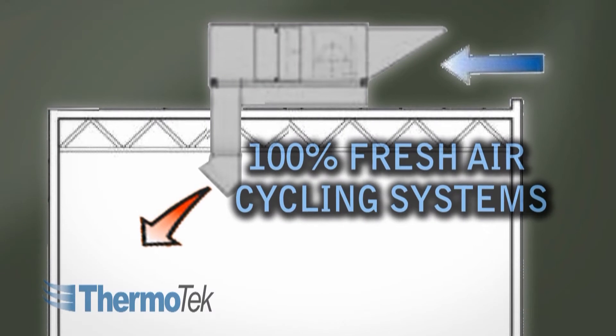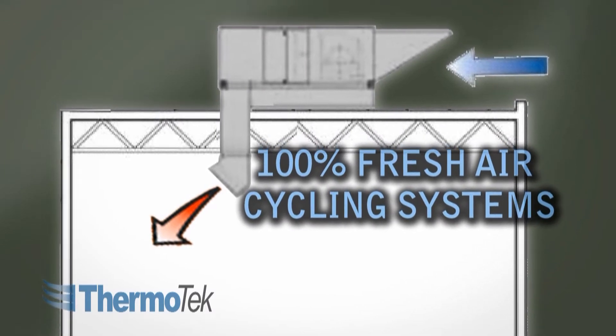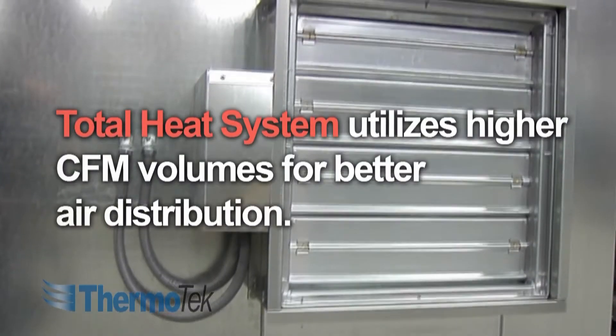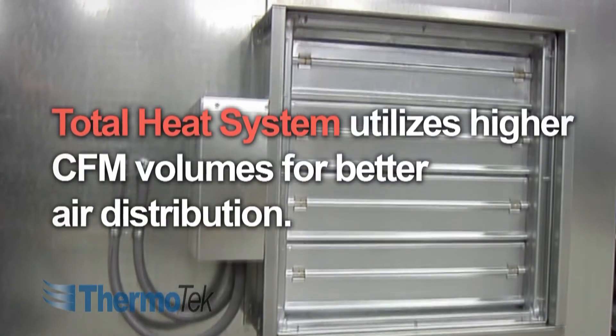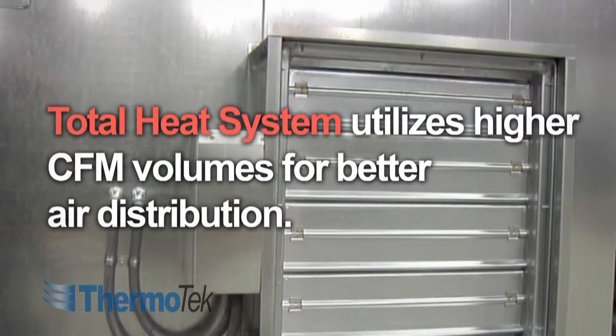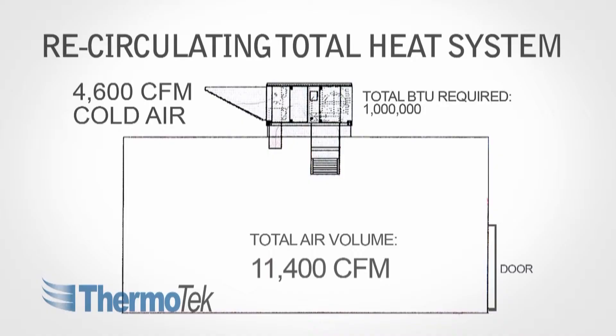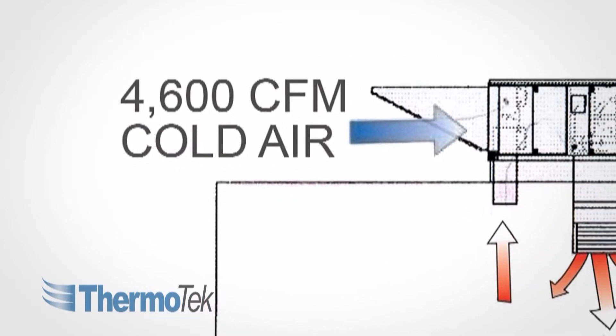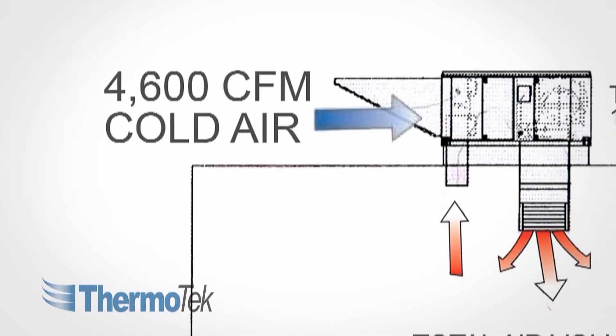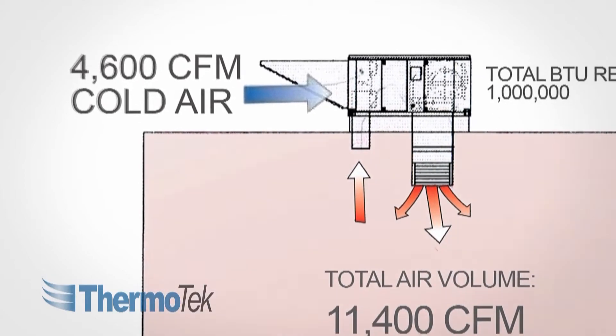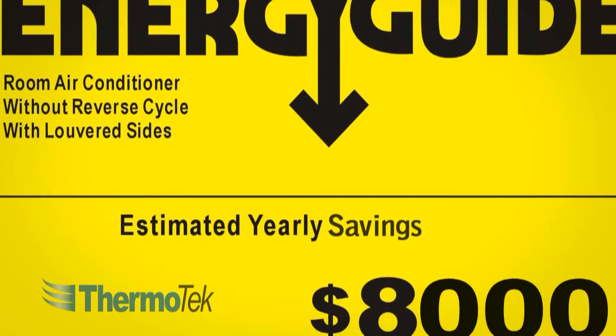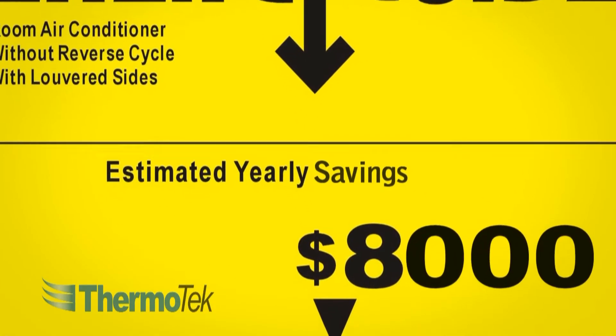Unlike the 100% fresh air high temperature cycling system, the total heat system utilizes higher CFM volumes for better air distribution. At the same time, by incorporating recirculation capability, the system is able to use less cold fresh air, in return reducing total gas consumption and producing astonishing energy cost savings.